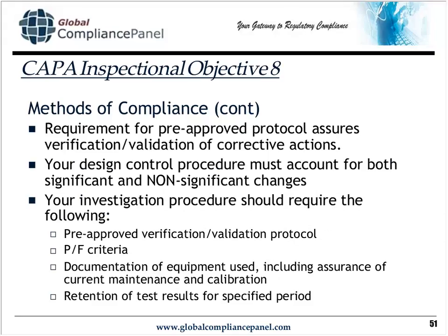Also, make sure that your procedure for validation, process validation, or design control procedure requires pre-approved protocols before testing is begun. And you want to make sure that your design control procedure accounts for both significant changes and non-significant changes, however you define those.